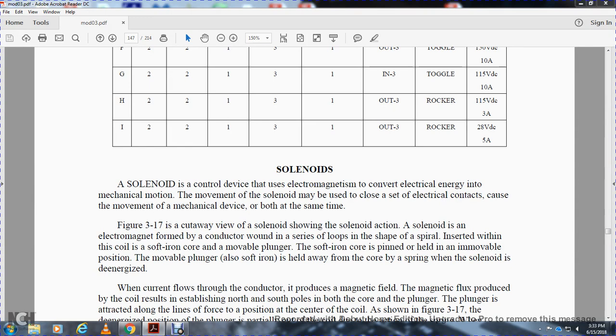The solenoid's electromagnet is formed by a conductor winding, a series of loops in the shape of a spiral, with a coil and a soft iron core and a movable plunger inserted within it. The soft iron core is pinned and held in an immovable position. The movable plunger of soft iron is held away from the core by the spring when the solenoid is de-energized.